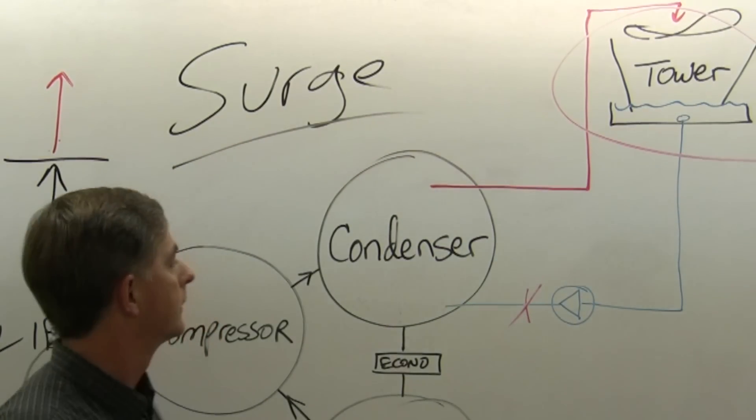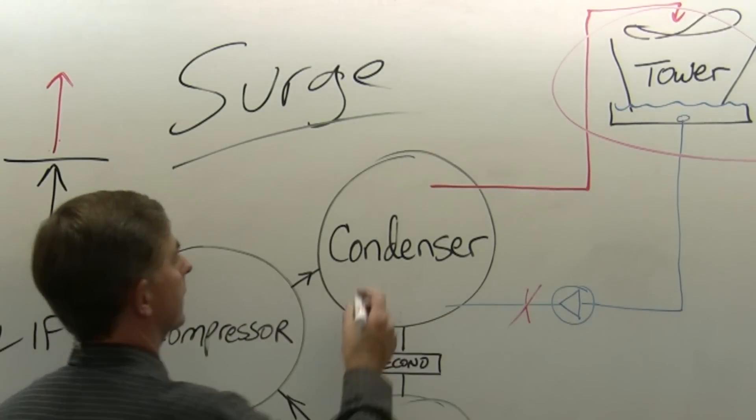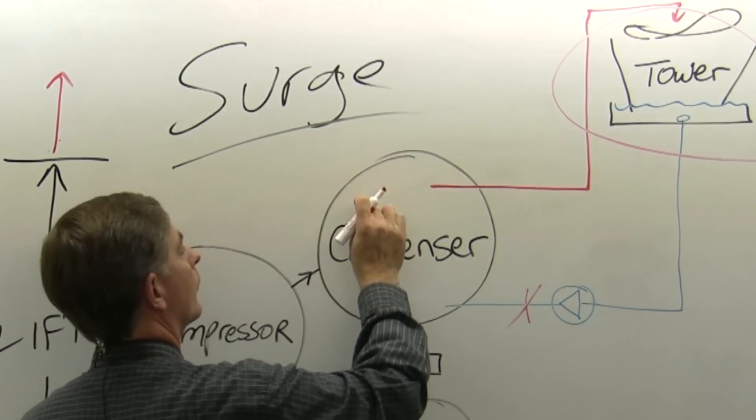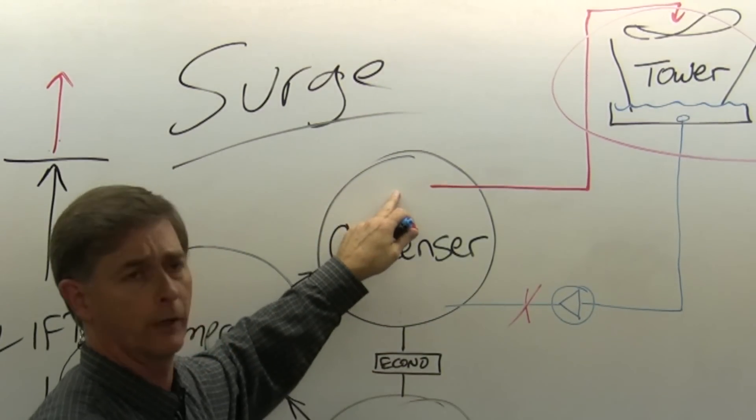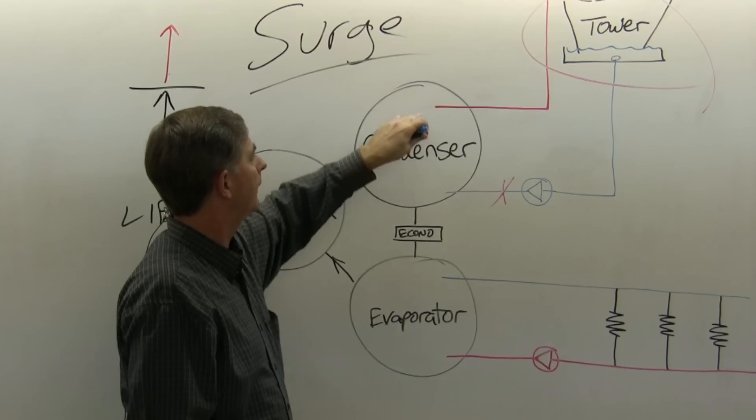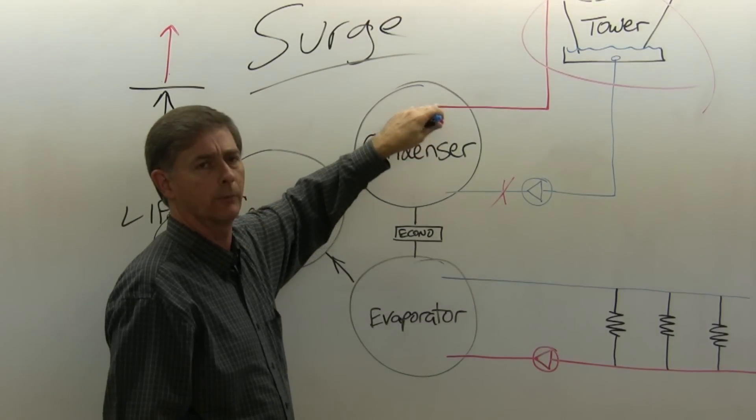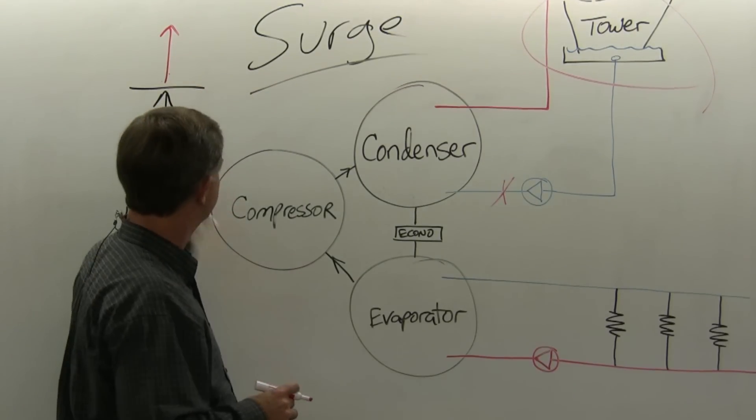Another cause is we can have air in the refrigerant. Air in your refrigerant or non-condensables of any type will cause this pressure to go up again to lift. Do you see a pattern here? Anything that causes a raise in temperature and pressure can cause surge.